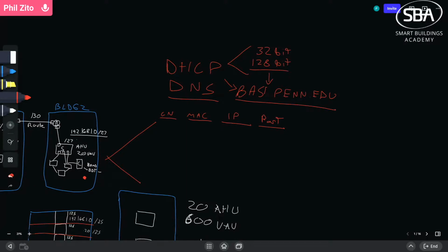All right. I didn't know you could use NAT on a BACnet router. Is that common? Not terribly common, but it is something you can do. It's typically used to take a public IP and translate it to a bunch of private IPs. Usually, getting the IP address pool is not terribly difficult unless you're with a larger customer.